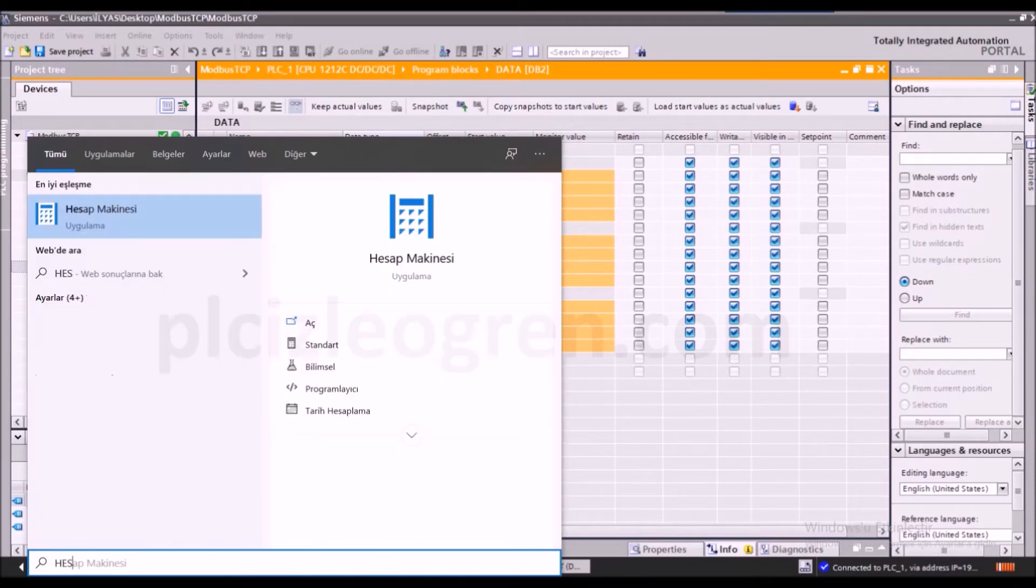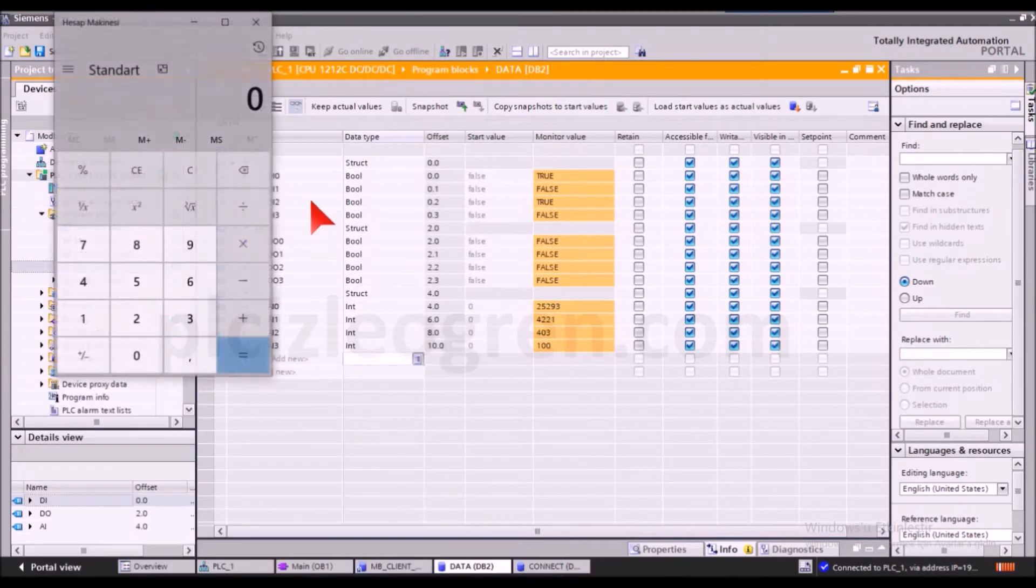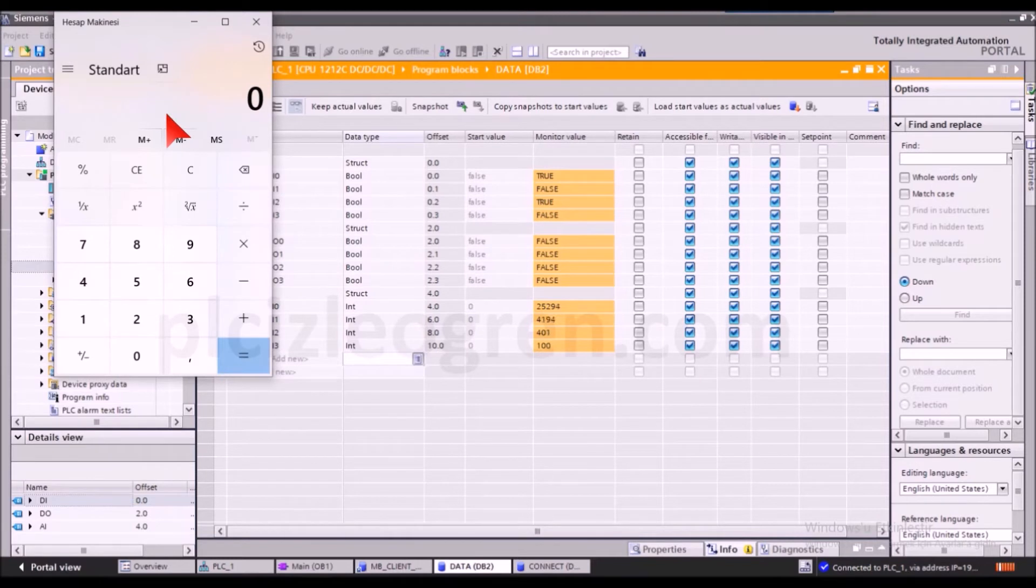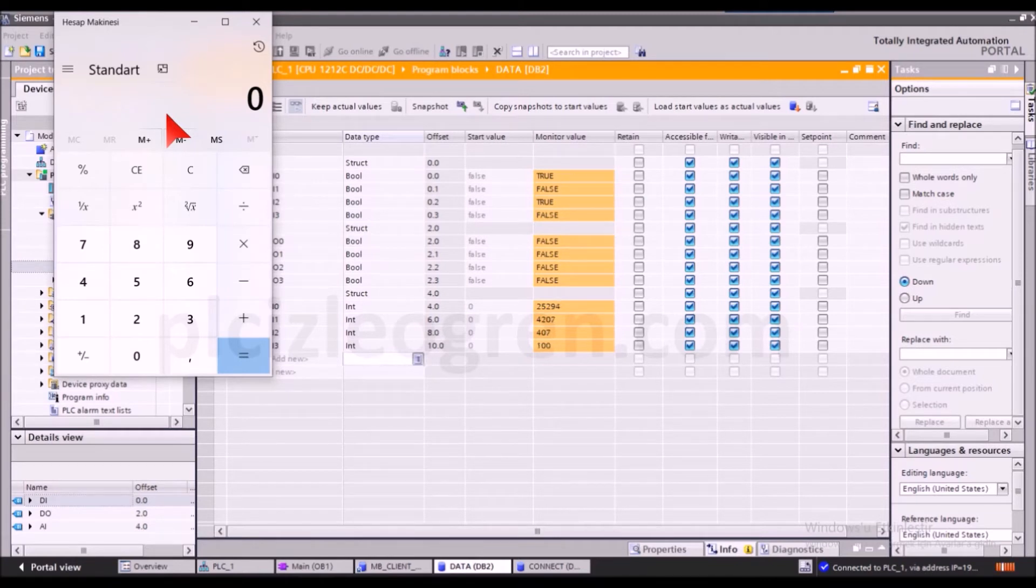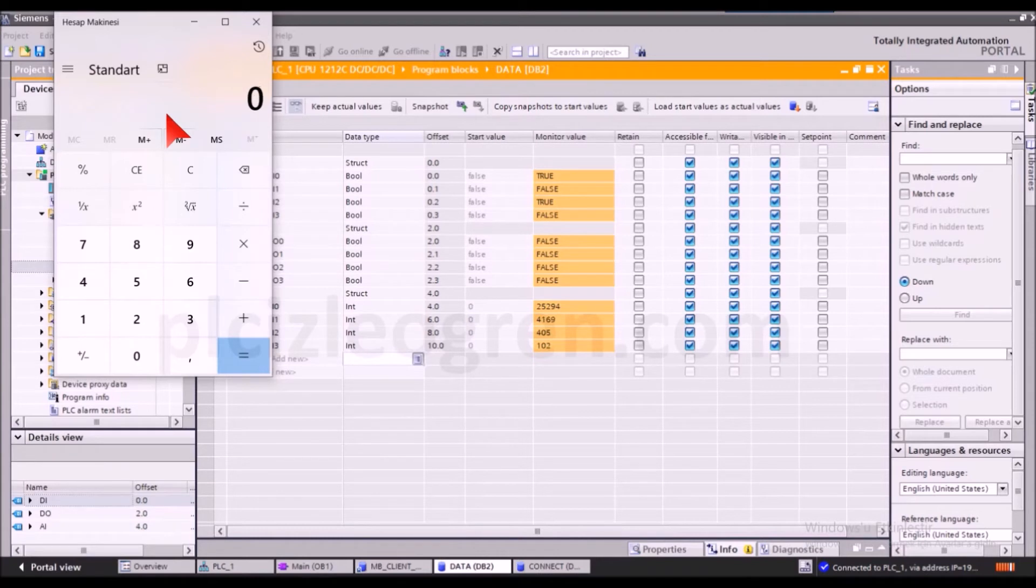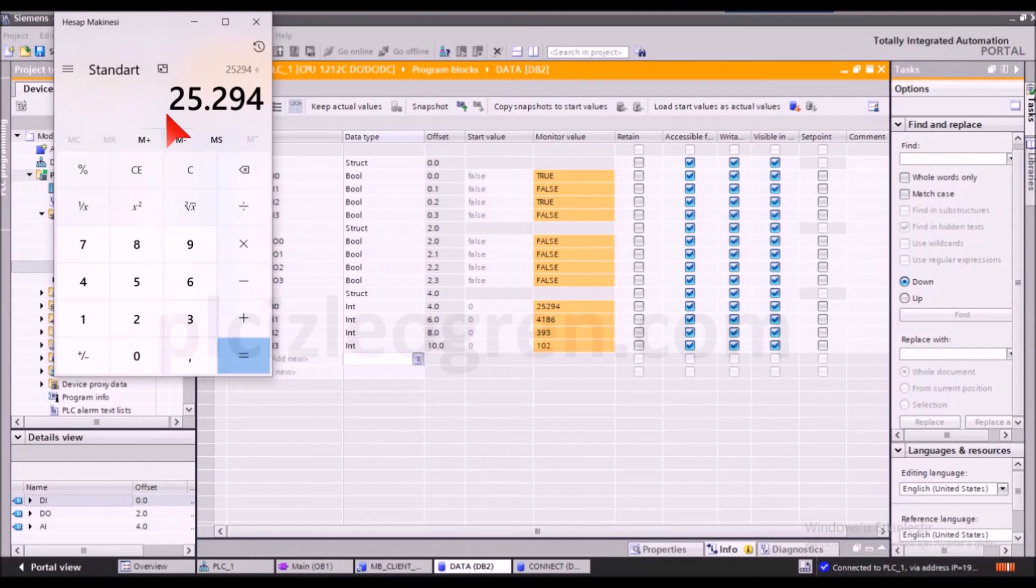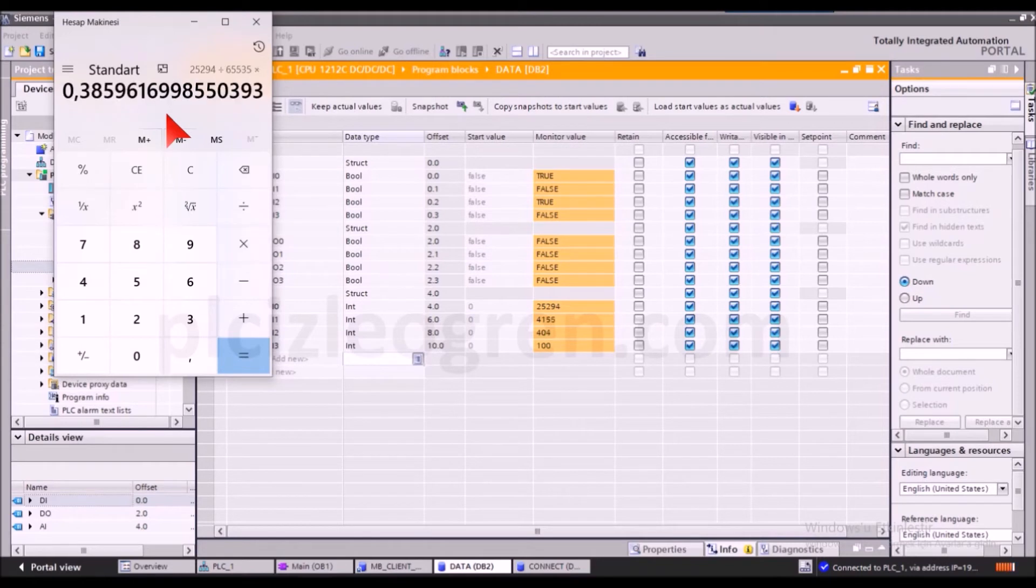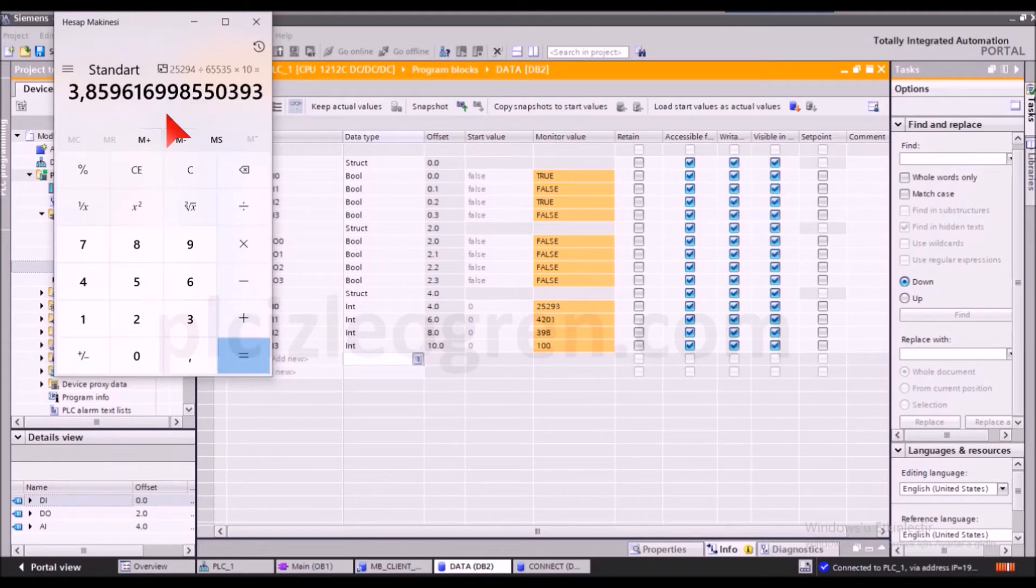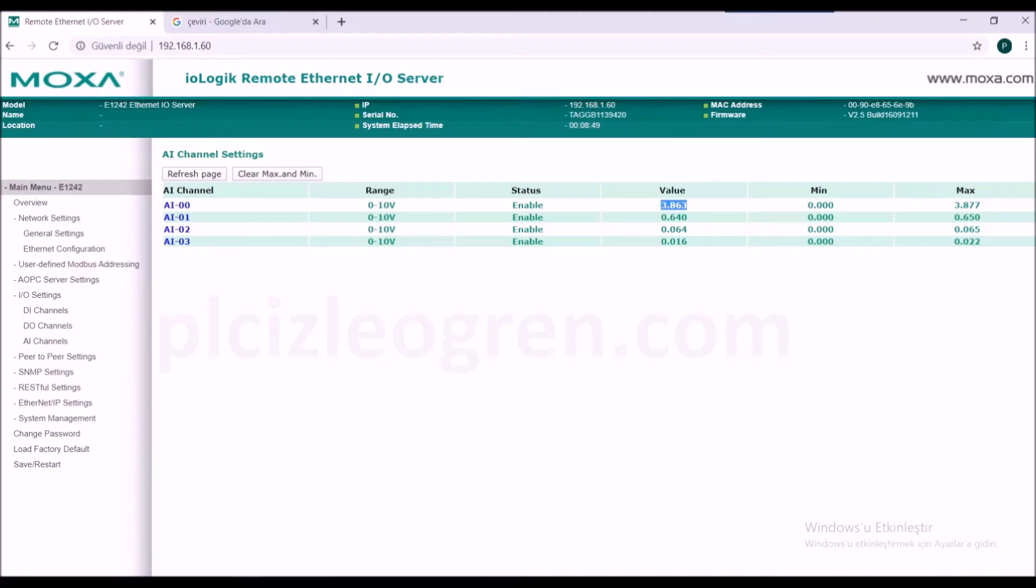I remember we've done this before. I can also scale this value in the PLC, but we'll use a calculator this time. The scaling will give me the actual value that I need. Let's take 25294 and divide that by 65535, which is the equivalent of 16 bits. If I multiply the result by 10, the scaling will be done. It's 3.85.